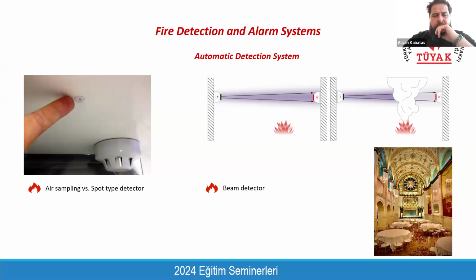And also, another alternative to these physical detectors, generally used in this kind of historical or wooden buildings. Instead of having spot type detectors, you can use this air sampling type, which is much smaller than the spot type detector. Or you can use these beam detectors, or call it optical beam detectors. You only have transmitters and receivers on the walls, and you will not see any kind of equipment on the wall or on the ceiling. If you will be responsible for renovation or refurbishment of this kind of historical buildings, or you have a very challenging architectural design of ceiling, instead of having spot type detectors, you can offer the electrical designer to use air sampling or beam detector.